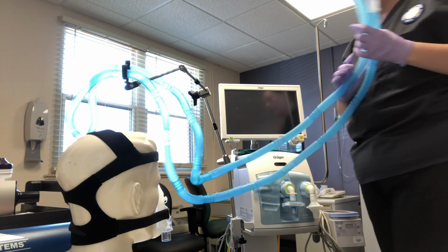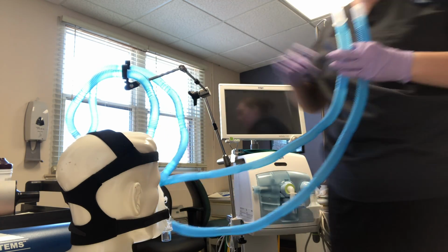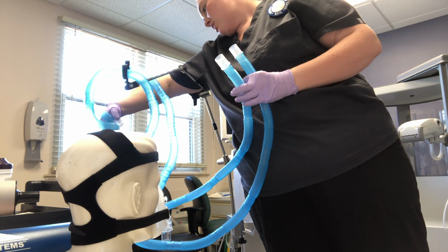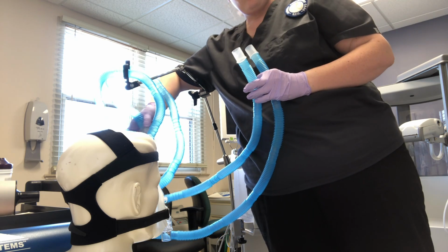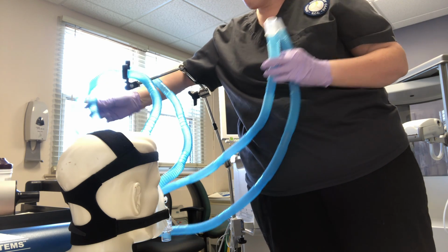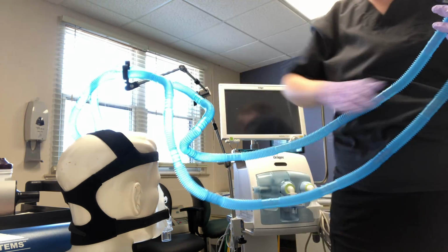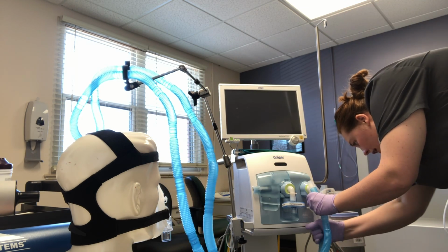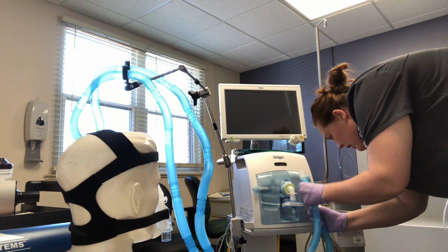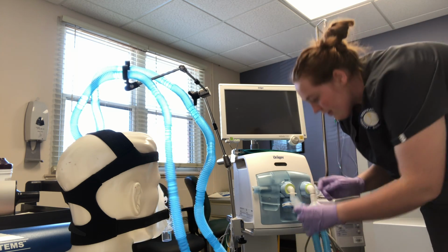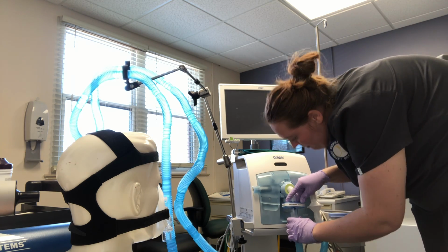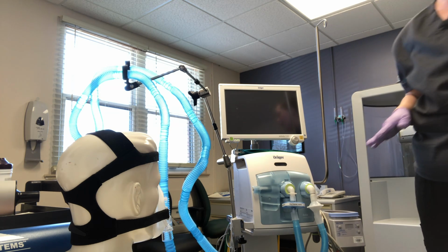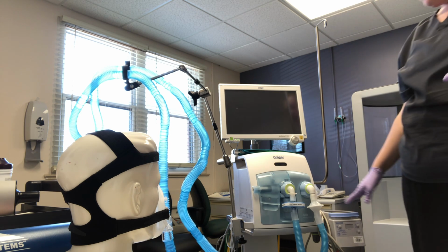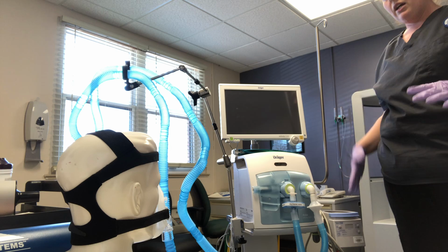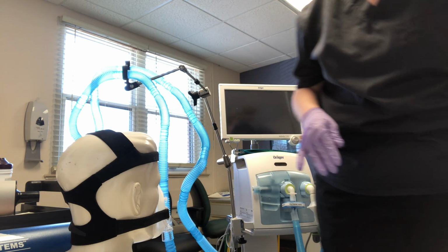Okay, so we know which side is inspiratory and which side is expiratory based on the patient side. So the side that has the larger opening is for the temp probe. So we know that that's for inspiration. So I can plug this side into my inspiratory valve, which means that the other side is for the expiratory valve, and we do have a filter going back into the machine for that. We can use heated circuit with humidity. For this video, we will not be doing that.